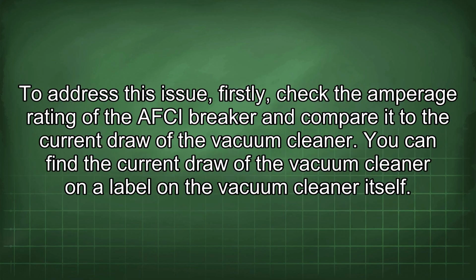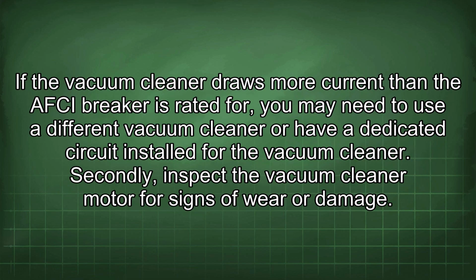To address this issue, firstly check the amperage rating of the AFCI breaker and compare it to the current draw of the vacuum cleaner. You can find the current draw of the vacuum cleaner on a label on the vacuum cleaner itself. If the vacuum cleaner draws more current than the AFCI breaker is rated for, you may need to use a different vacuum cleaner or have a dedicated circuit installed for the vacuum cleaner.